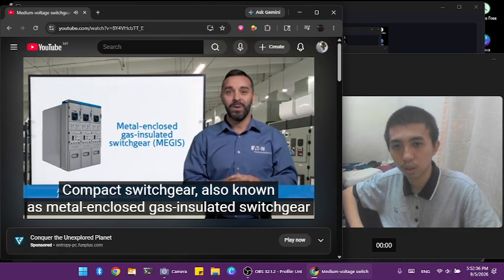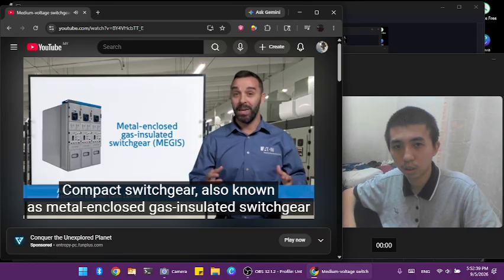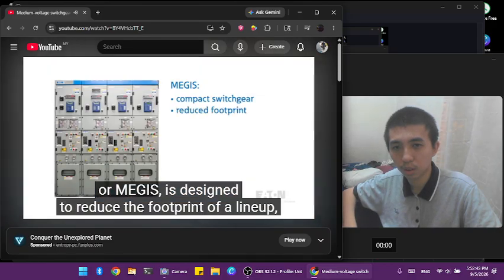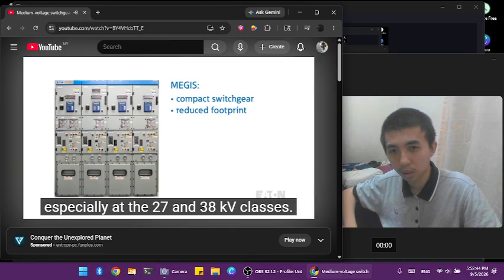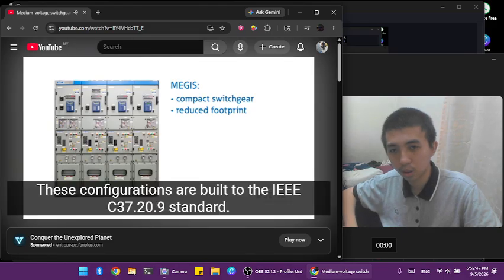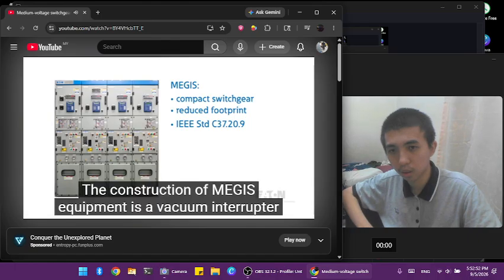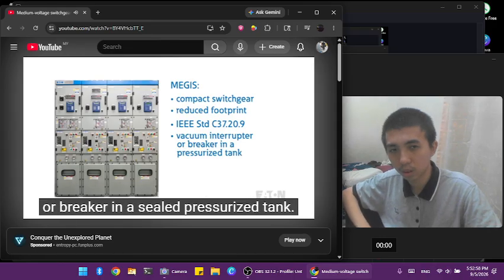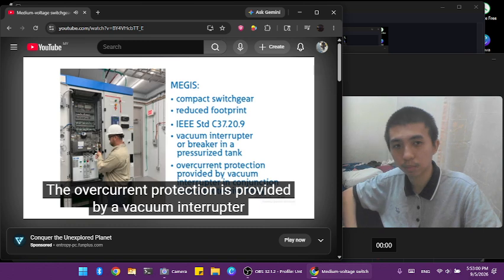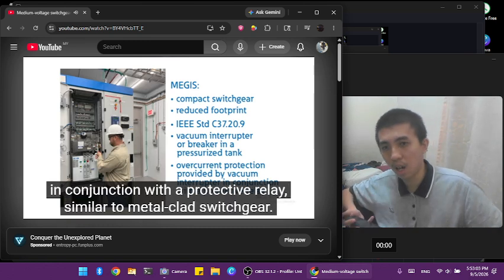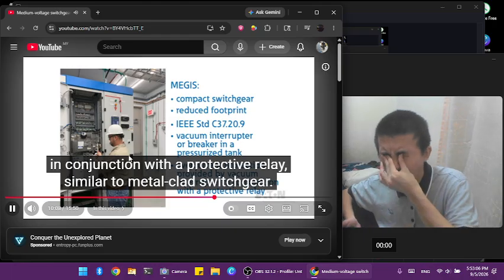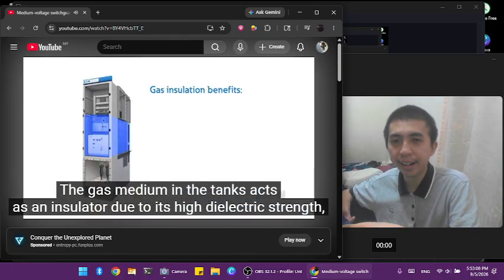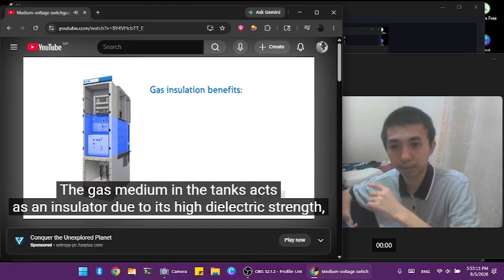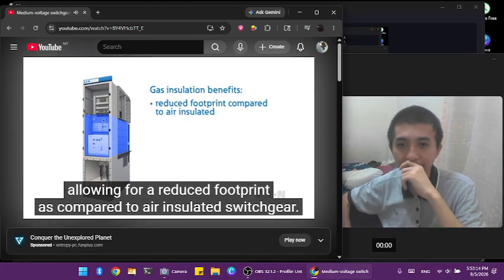Compact switchgear, also known as metal enclosed gas insulated switchgear or MEGIS, is designed to reduce the footprint of a lineup, especially at the 27 and 38 kV classes. These configurations are built to the IEEE C37.20.9 standard. The construction of MEGIS equipment is a vacuum interrupter or breaker in a sealed pressurized tank. The overcurrent protection is provided by a vacuum interrupter in conjunction with a protective relay, similar to metal-clad switchgear. The gas medium in the tanks acts as an insulator due to its high dielectric strength, allowing for a reduced footprint as compared to air-insulated switchgear.